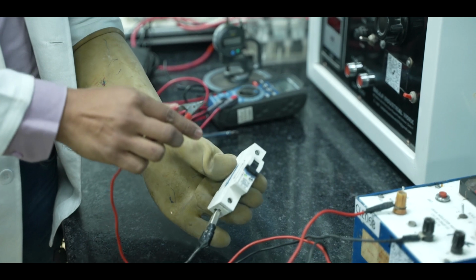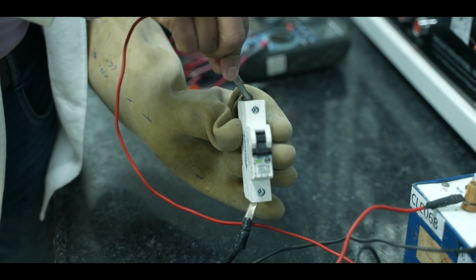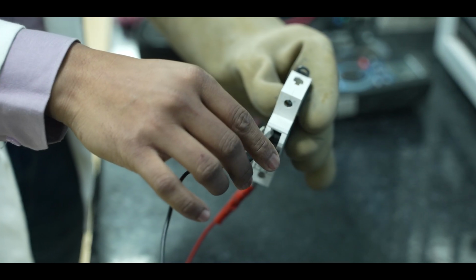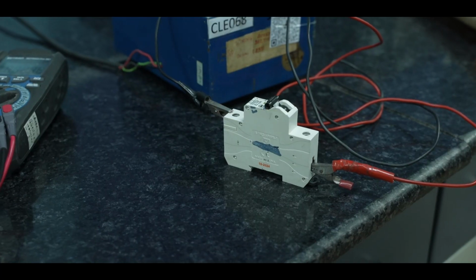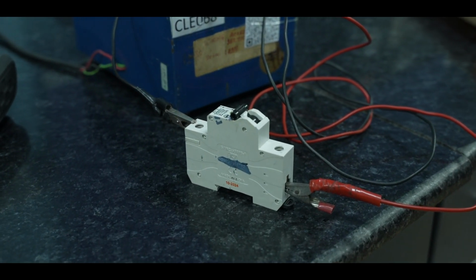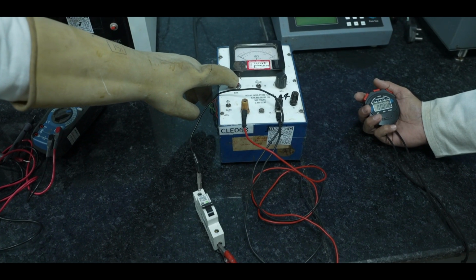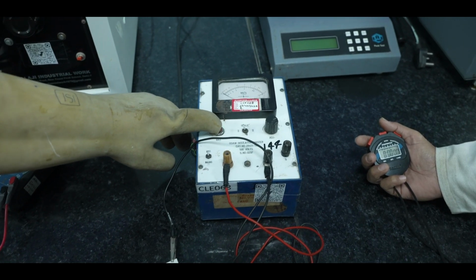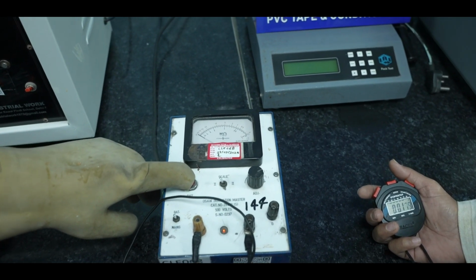Insulation resistance and dielectric strength test. First, we measure the insulation resistance between auxiliary circuits connected to each other and the frame, as well as between isolated parts of the auxiliary circuits. A test voltage of approximately 500 volts DC is applied for 1 minute. The insulation resistance must be no less than 2 megaohms.